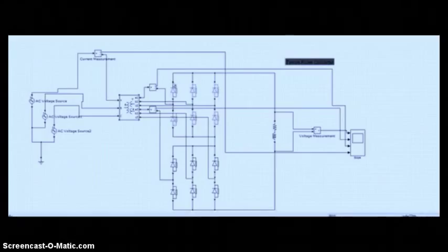This green one shows a standard 3-phase full bridge rectifier, and this one also is a standard 3-phase bridge rectifier. This delta connected secondary is connected to the black converter, with this A phase being measured for the current, and this Y connected one is connected to the green converter. So 1 secondary with the green converter and 1 secondary with the black converter. This is an optional device, but I want to measure the current and see if there is actually a 30 degree delay in the current or not, which I have earlier claimed.